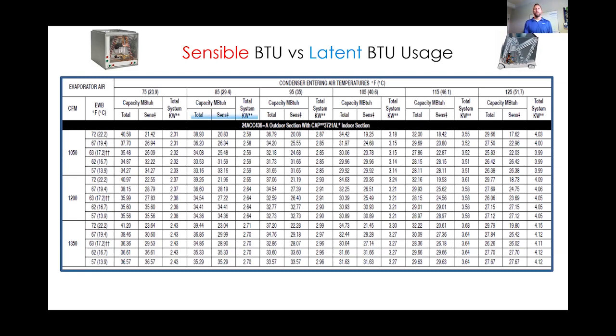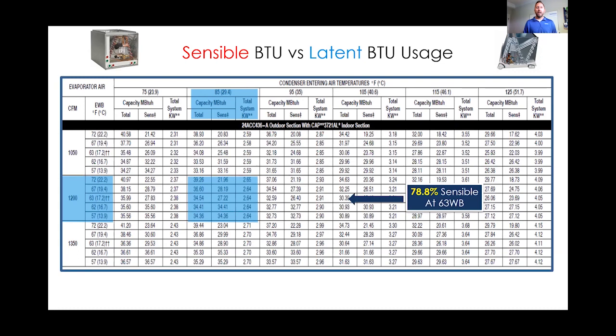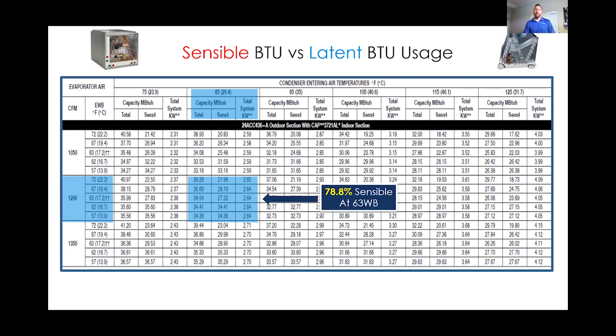So I'm using a 3-ton analogy here. If I take this chart and I see that it's an 85-degree outdoor day, I've got 400 CFM per ton, so 1,200 CFM, that's in the far left column. What this manufacturer is telling me is, if my cursor shows up for you all here, what they recommend, that's what these two crosses mean here. What they're recommending is that the indoor design condition should be 63 degrees of wet bulb, entering wet bulb. If that holds true, then this system, the way it's designed, installed, and commissioned, will deliver a 79, we'll call it 79% sensible ratio, which means 79% of that evaporator coil or that cooling coil is doing its job in just cooling the air. But that just means that 21% of that coil is actually used for dehumidification. Not a great dehumidification strategy.